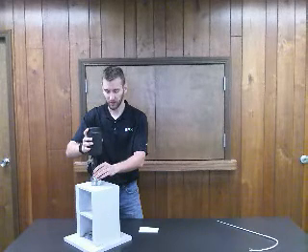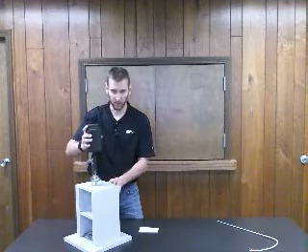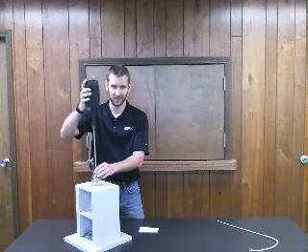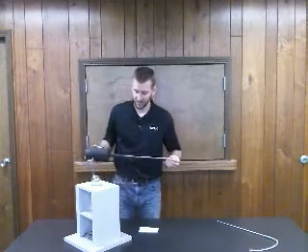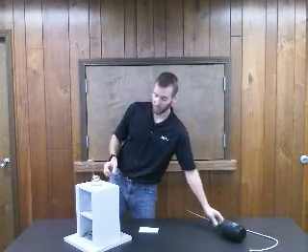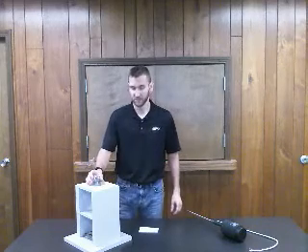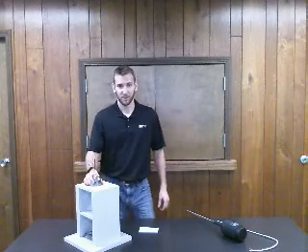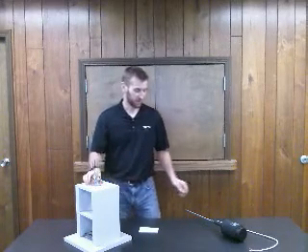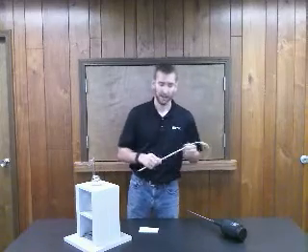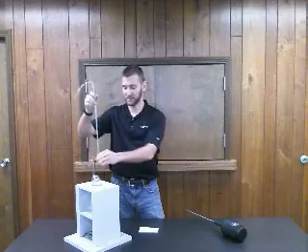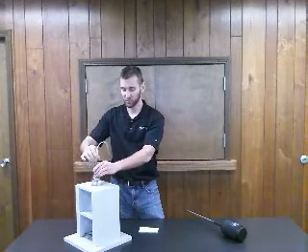Now, as the ice mantle begins to form around the well, we will be looking for roughly a 1/4 inch thickness. And this will tell us that we have met the critical condition for the triple point ice mantle thickness. Once this is done, we'll have to break that mantle free of the well. A long rod would be heated by friction or using a little flame, and then it would be placed in this well to where it could radiate heat.